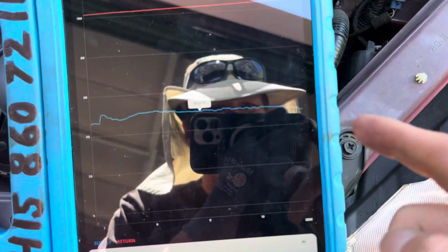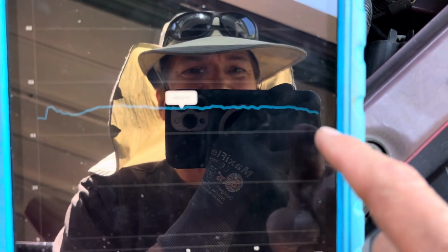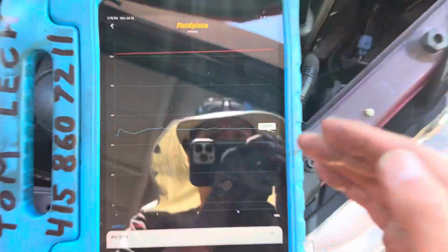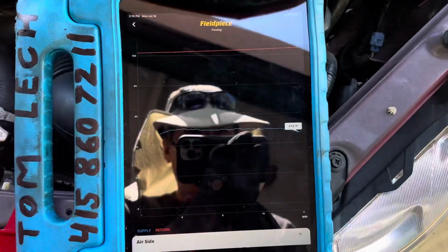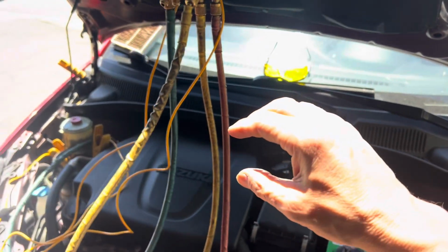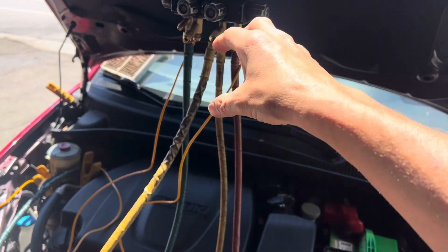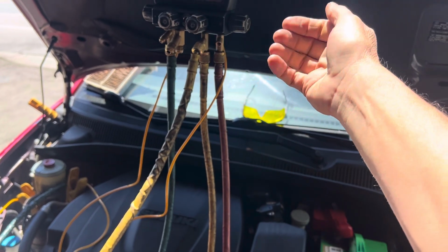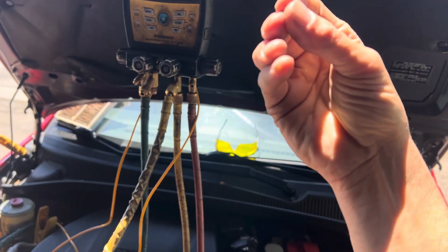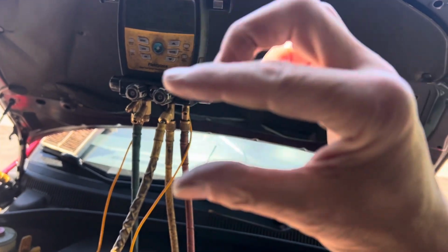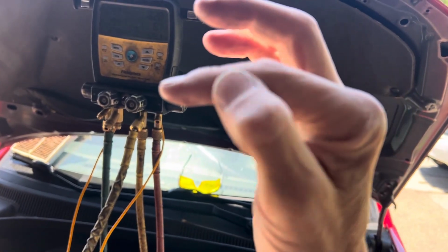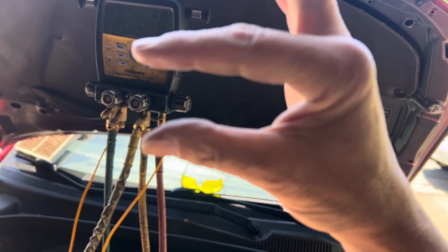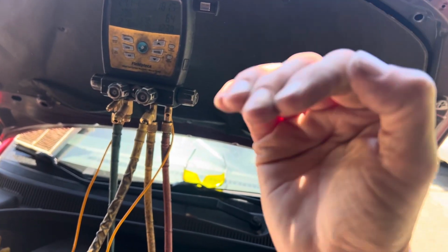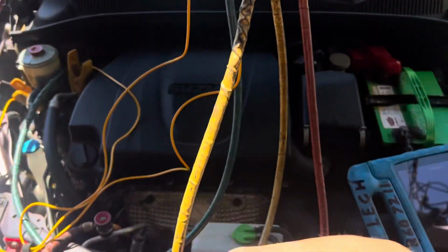So you see I jumped up the idle to what was that, 1100 RPMs, and now you see the temperature coming down. It's moving more pounds of refrigerant across the expansion device. There's more liquid refrigerant capable of absorbing more heat that is coming across the fins. The fins are attached to the tubes, and where they touch the surface of the tube material, inside is the refrigerant. That heat has to pass to the refrigerant and then go back through the loop again. And look at our temperatures coming down.